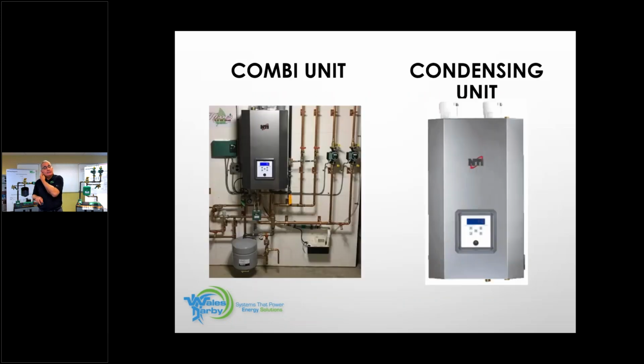Okay. Condensing, combi units, and just straight condensing heat only boilers. We sell them. That is the brand that we represent. We're very proud to do that brand. They need to be piped specifically. They need to be piped in primary, secondary. You could do moose antlers. We could do all kinds of things, but you're going to need to do them in primary, secondary.